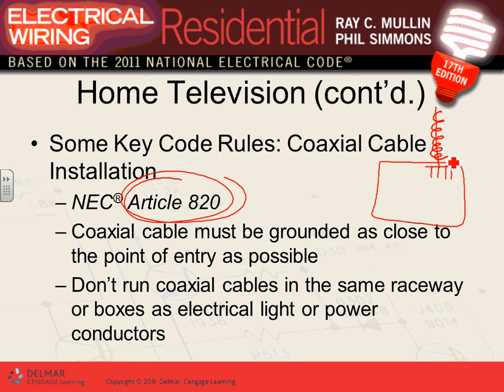Right here, guys, you are to ground the shield. This point, as the coaxial cable enters the house, is called the demarcation point. By code, the demarcation point is where the coaxial cable or phone cable enters the house or building. The code requires you to ground the shield of that cable right at that point.